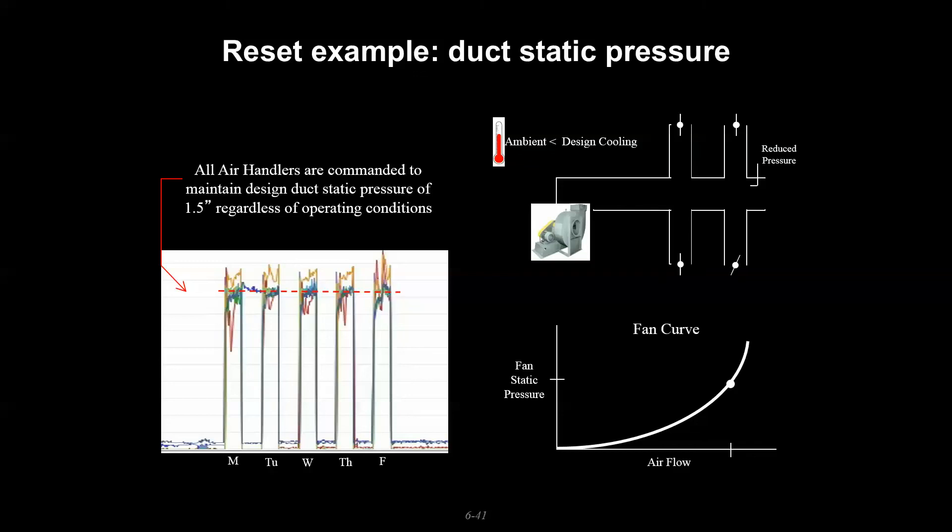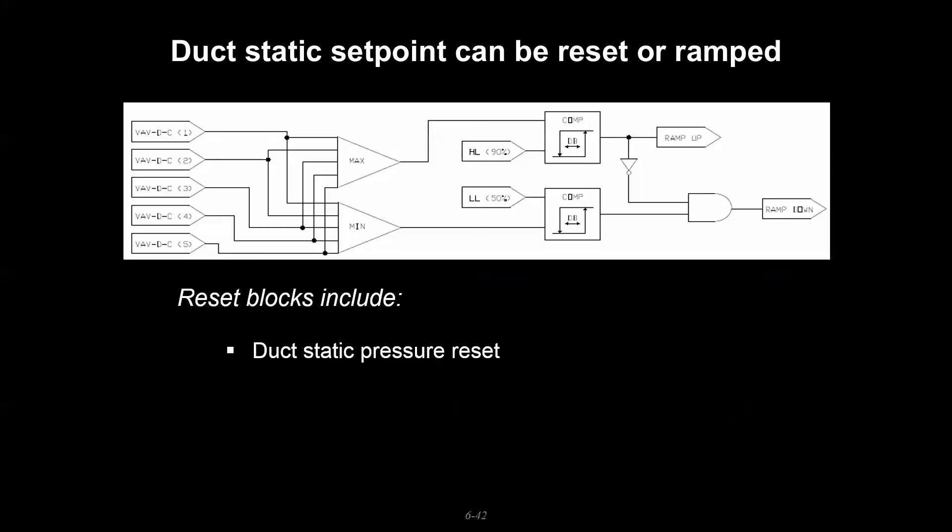That's some of the logic about why we reset some of our setpoints, and we can do that with duct static pressure. We do that with a lot of hydronic temperature setpoints on the supply side. We may also do that on the air side with air being discharged from a coil. We may also do that on the air side on the coil discharge setpoint.